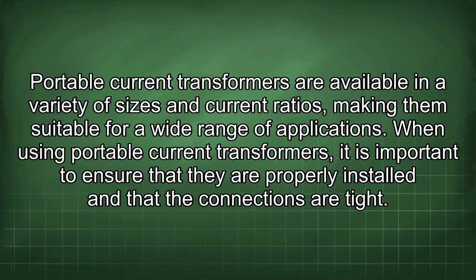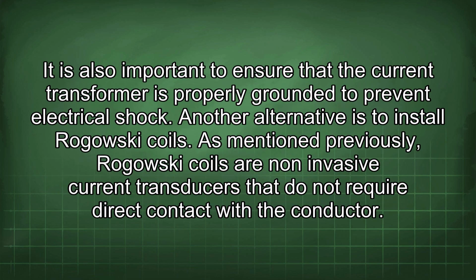When using portable current transformers, it is important to ensure that they are properly installed and that the connections are tight. It is also important to ensure that the current transformer is properly grounded to prevent electrical shock. Another alternative is to install Rogowski coils.